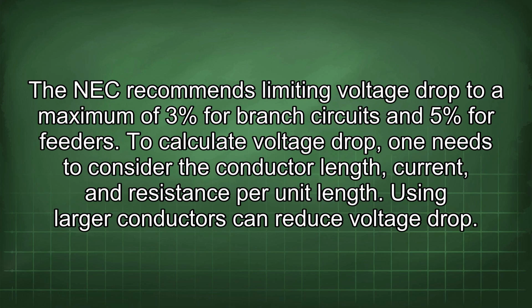The NEC recommends limiting voltage drop to a maximum of 3% for branch circuits and 5% for feeders. To calculate voltage drop, one needs to consider the conductor length, current, and resistance per unit length. Using larger conductors can reduce voltage drop.